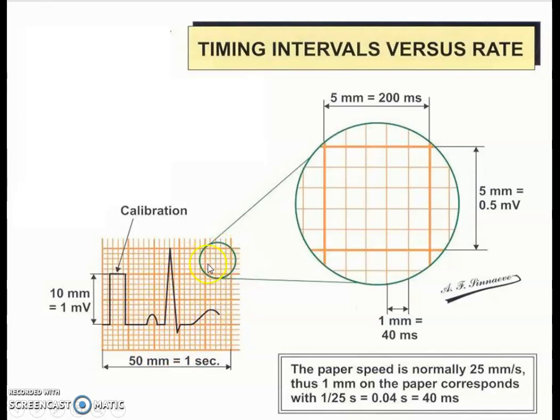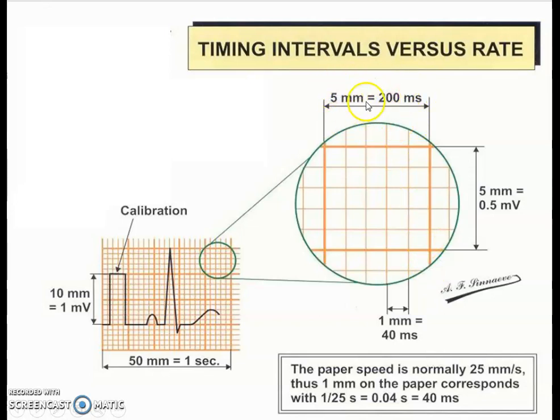If you zoom in, this larger box, you will find that the vertical height of 5 mm is equivalent to 0.5 millivolt. Now if you look at the horizontal division, if the paper speed is set to 25 mm per second, then 1 mm on the paper corresponds to 1/25, which means 0.04 second, or 40 milliseconds. So as there are 5 divisions, 5 multiplied by 40 gives a total of 200 milliseconds. These scales are generally used to calculate the height and width of the individual pulses as well as the complex of the ECG signal.